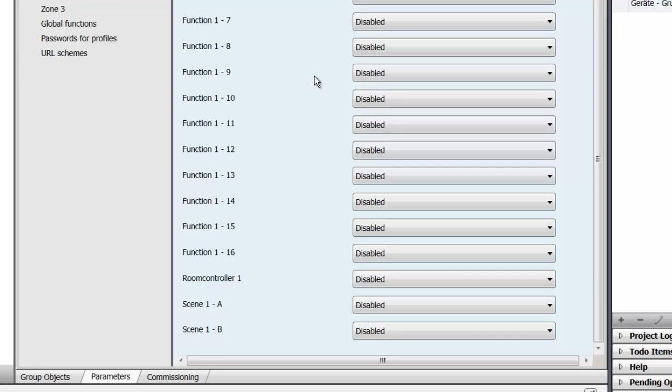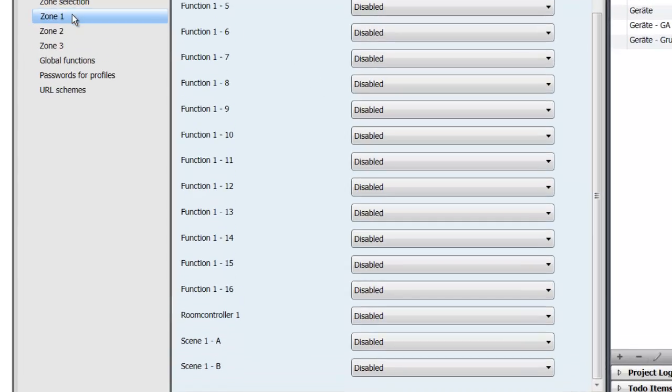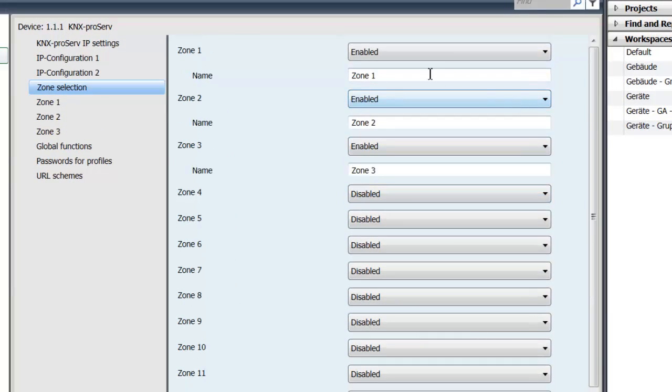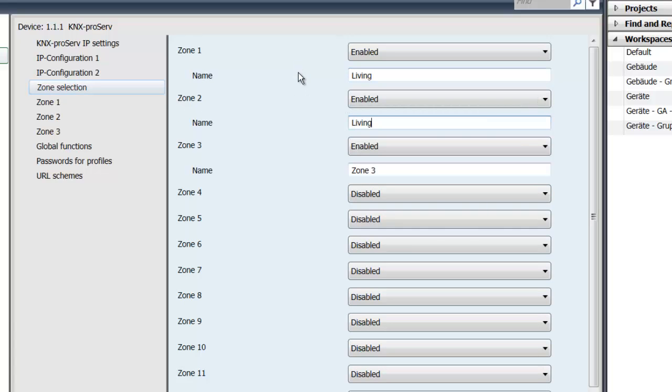Let's say you need more than 16 functions within one zone because you have a huge living area where you have a lot of blinds and a lot of light circuits you need to control. Then you can easily go into zone selections and give those two zones the same name. So in our case this would be living and then those zones will be merged. So you only have one living zone within your apps, which will then give you 32 objects to be added to that zone. You can extend that up to as many zones as you'd like. So let's say our third zone here is our master bedroom.